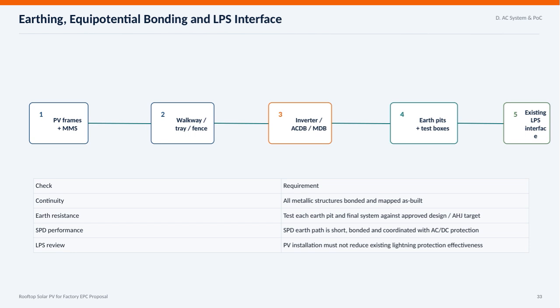The table here outlines essential requirements. Continuity is crucial. This means that all metallic structures must be properly bonded and documented as built to ensure safety and functionality. We also must test earth resistance for each earth pit and the overall system, making sure they meet the approved design targets or authority having jurisdiction standards.